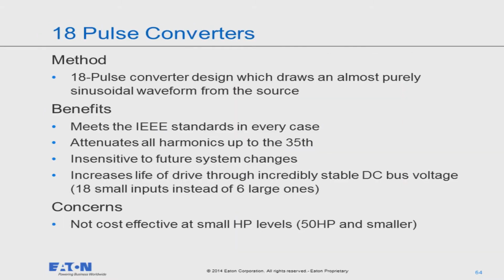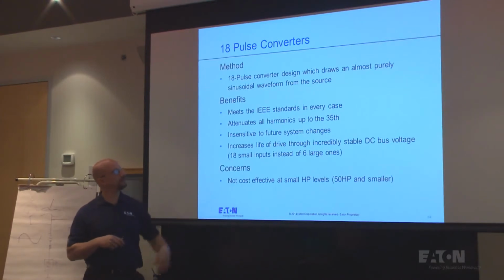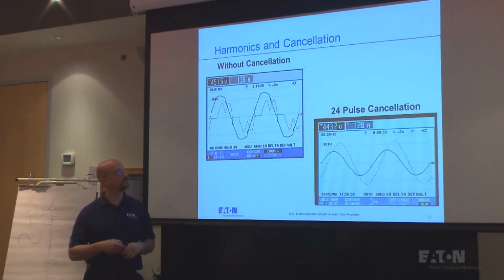And I mentioned earlier that our 24 pulse, our medium voltage drives are 24 pulse. So anyway, you have to think about which harmonics are going to be attenuated and reduced, and that's really a good way to do it.